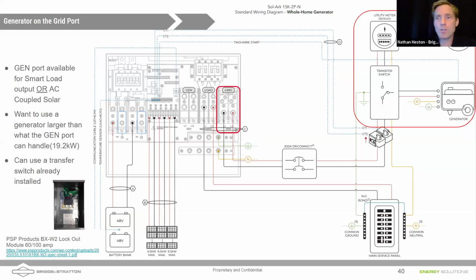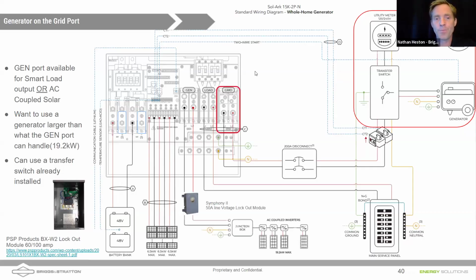Now, our 26K generator can be brought in through a transfer switch into the grid port on the Sol-Ark 15K, and that leaves that generator port open. The Sol-Ark can still use a two-wire signal to start and stop the generator. It's going to run off of batteries first, and if the batteries get low, it can send that two-wire signal to start. So you don't lose that ability just by putting it on a transfer switch. But it also leaves the generator port there for AC coupled solar.